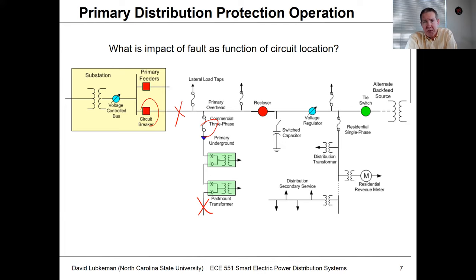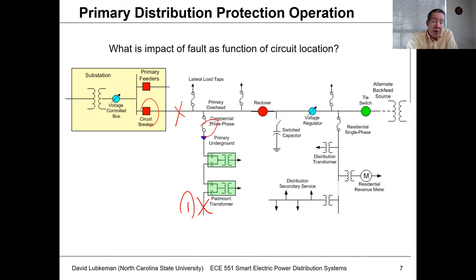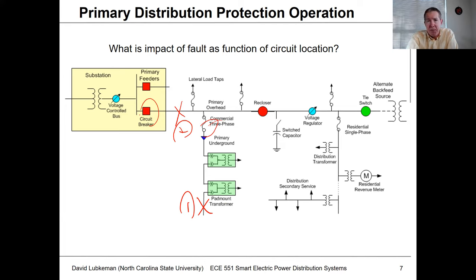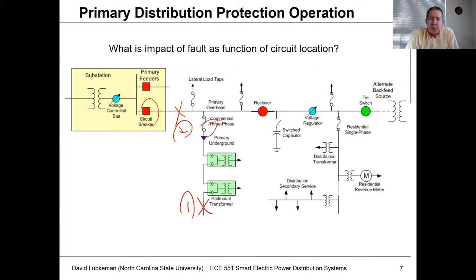What's the difference between these two events? In the first event, I would just lose the customers below that fuse. But if I had a fault at location number two and that circuit breaker trips open and stays open, then all the customers on the circuit are going to be out. So we're going to have these different fault events, but depending on the location of the fault event, it's going to have a different impact in terms of the number of customers that are out.